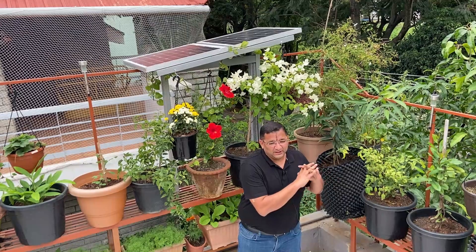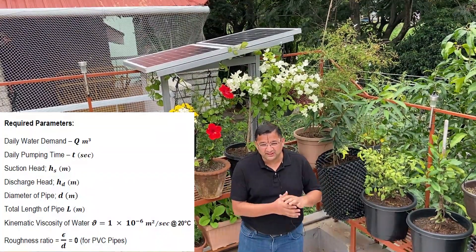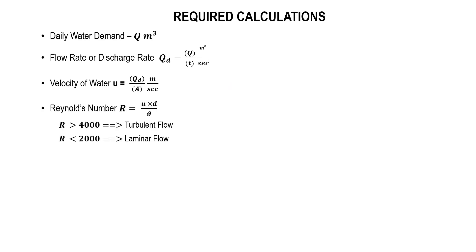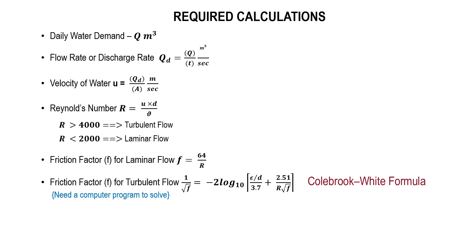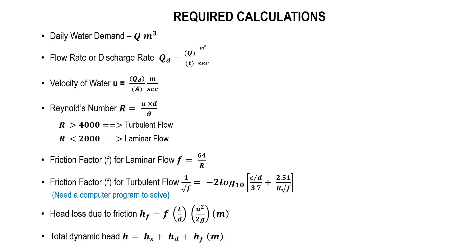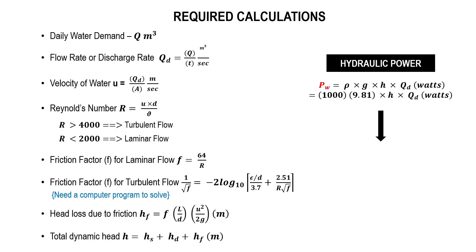Strictly speaking, to design a pump to lift water we need many parameters. First, we need to know the total volume of water required per day, then estimate the flow rate depending on pumping duration, then determine the velocity of water, then calculate the Reynolds number, and determine whether the flow is turbulent or laminar. Depending on the flow type, we estimate the friction factor using the Colebrook-White formula, then determine the friction head loss via the Darcy-Weisbach formula. Finally, we plug everything into the hydraulic energy formula: density of water × acceleration due to gravity × total dynamic head × flow rate, which gives the pump capacity required.